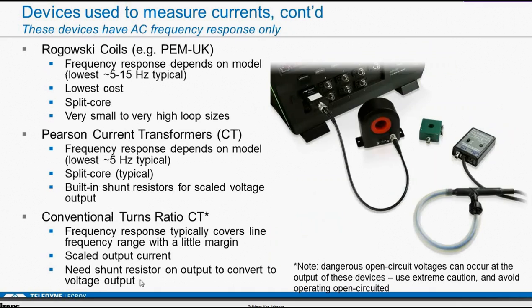So now, if you don't need DC, these various devices have an AC frequency response, meaning their frequency response might be from a few hertz, like 3 hertz or 5 or 20 hertz, up to something higher, but they don't reach down to DC. So you can never get a DC level. You can't measure a DC bus current with them, but they still have their place. If all you want to do is measure utility voltages and currents, a Rogowski coil has a frequency range that fits nicely in that range, and they make some that reach down to very low frequencies and also reasonably high frequencies for some other specialized measurements as well. They're split core; they can be opened up and fit around, and the cost is generally very low.